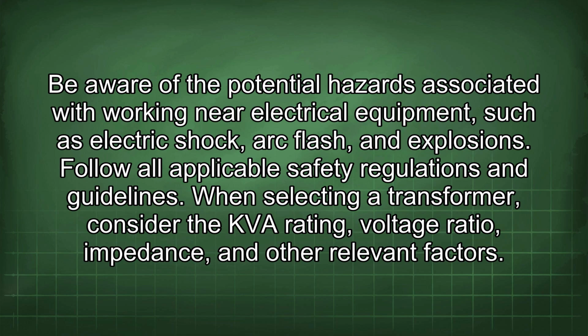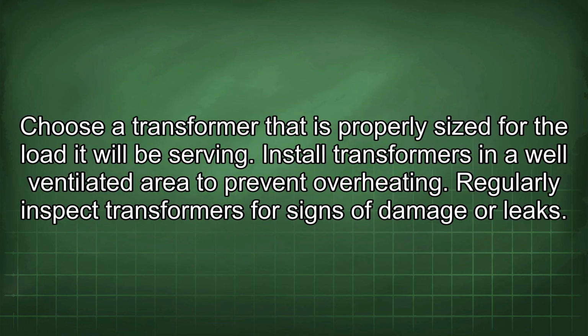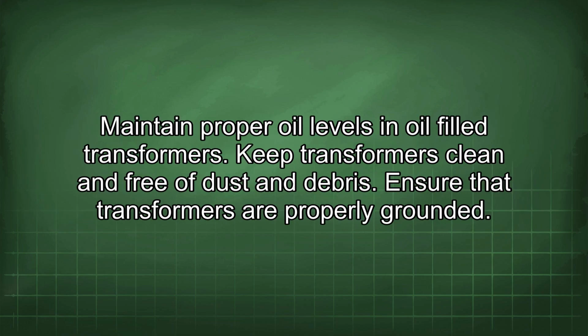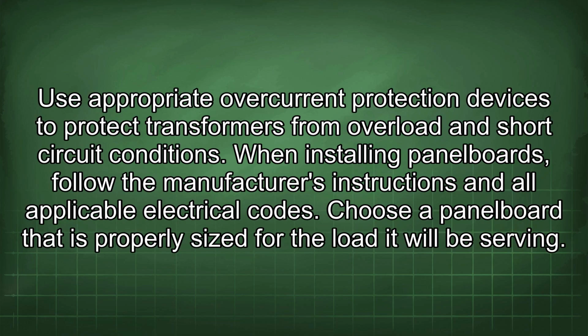When selecting a transformer, consider the kVA rating, voltage ratio, impedance, and other relevant factors. Choose a transformer that is properly sized for the load it will be serving. Install transformers in a well-ventilated area to prevent overheating. Regularly inspect transformers for signs of damage or leaks. Maintain proper oil levels in oil-filled transformers. Keep transformers clean and free of dust and debris. Ensure that transformers are properly grounded. Use appropriate overcurrent protection devices to protect transformers from overload and short-circuit conditions.